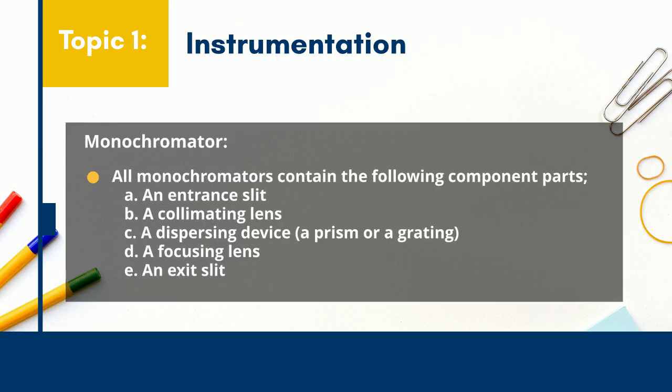Next, we have the monochromator, which splits the radiation beam into its component wavelengths by the grating or prism, and then followed by a narrow slit. This slit ensures that the radiation is of a very narrow waveband. That is why it is called monochromatic.